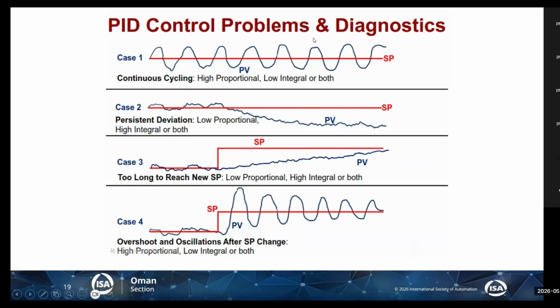And this is a thumb rule, but again, practically things are not 100%. We cannot stick to this 100%, but it can give you some reference. It can give you some hints where to troubleshoot. So if you see this behavior, typically this is because of high proportional or low integral or both. If I have a very high proportional, as I said before, proportional action makes the controller fast, and we always want it to be fast, but too fast is not very good. It can make it oscillate.